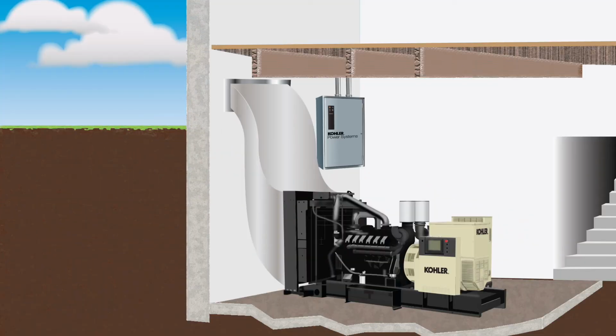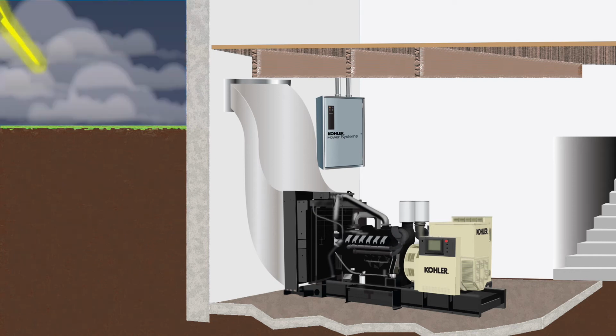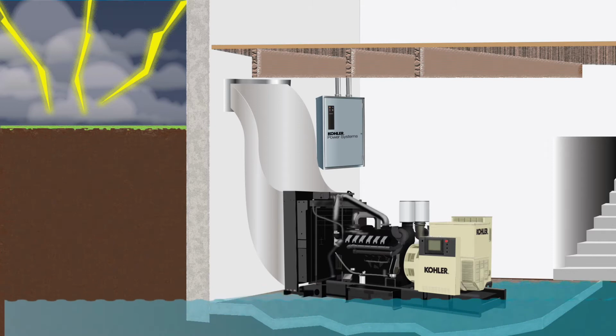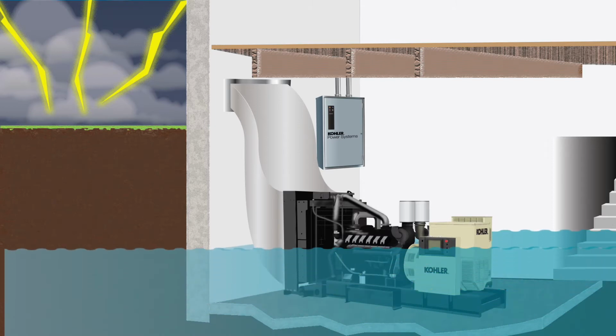Generators installed in basements prone to flooding were another problematic issue. Major storms produce significant flooding with storm surges and heavy rain. After the utility fails, emergency power takes over. However, as the ground becomes saturated and can no longer absorb any more water, it causes the water table to rise. As the basement becomes flooded with rising floodwater, the set shuts down and all power is lost from both the utility and standby generator.